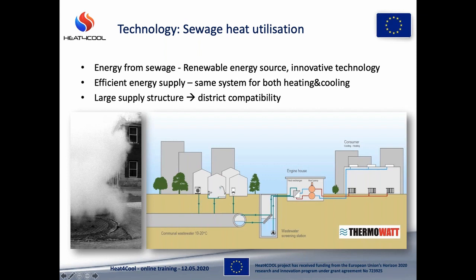We use the filtered water through pumps and conduct this flow into a heat exchanger. After heat exchange, we feed the heat pump. Once the heat pump heats up the building in heating mode, the cold water comes back through the heat exchanger, and after this we flush back the solids, and the colder flow goes back to the sewer in heating mode.